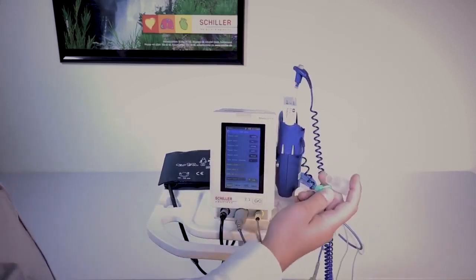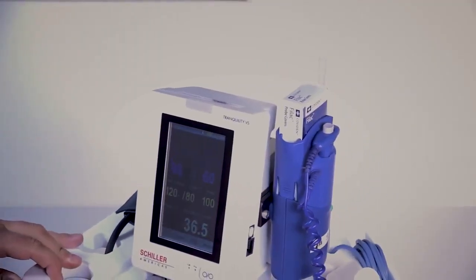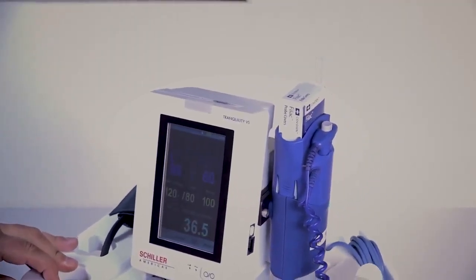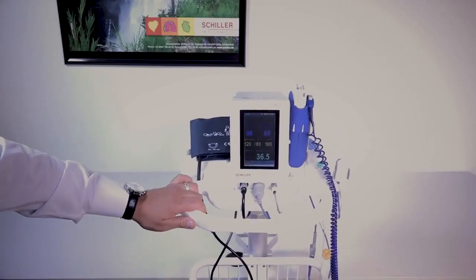The parameters are plug and play with three patient modes. It comes with fully configurable audio and visual alarms for all parameters, and the data trends are transmittable to your EMR. If you don't use an EMR, we also offer an onboard printer. Overall, the Tranquility VS is a compact vital signs monitor with a variety of functionalities that you will not be able to find in any other similar products.